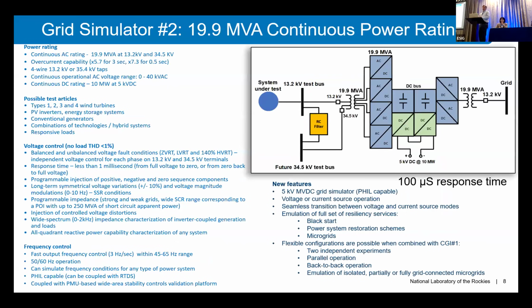Our second grid simulator, CGI2, controllable grid interface, we added about 2 years ago. So it's a 20 MVA system, and we commissioned it maybe 3 years ago. Changes from CGI1: we added a 34.5 kV tap to our output transformer. So we can do 13.2 kV and also 34.5, and we can go, I think, 50% over that. So we can go up to about 50 kV on the high side. It's faster, with a 100 microsecond response time.